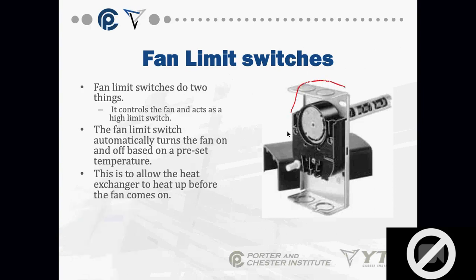Let me turn my pen on. This device is usually mounted on the front of the oil furnace, and you also see these in gas furnaces as well. The portion here is called a helix. It sticks into the plenum. By plenum, I mean the area where the room air is circulated through, not into the combustion air, which is where the flame is, but the area of the furnace where room air is circulated through, and it heats up. As this helix area heats up, it will start turning this dial, because this helix is bimetal, and when you have a helix of bimetal, it can create rotation as it heats and cools.